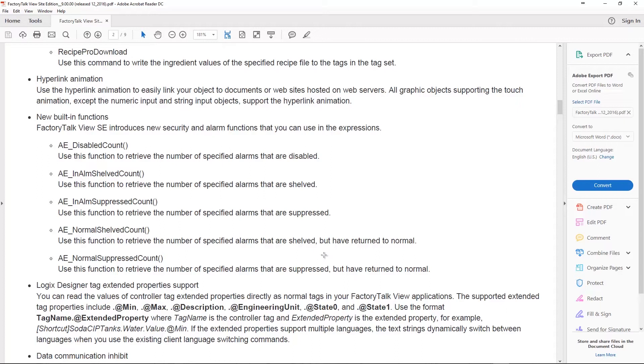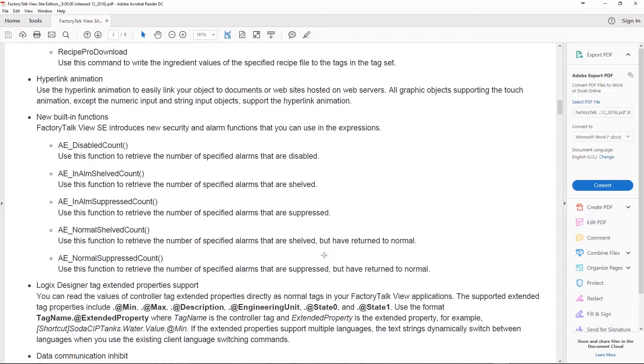But here's probably the biggest feature here of the version 9.0 is the Logix Designer tag extended property support. So you know for a while now in Studio 5000 we've been able to add an @Min and @Max and @Description and @Engineering Unit and @State to our tags. This is all kinds of stuff we used to do with HMI tags but once we get direct referencing with Logix, why would we want to create a tag database anymore? But on the flip side the downside was we still by doing direct referencing we had no way to do a min, a max, a description and whatnot like we did with HMI tags. But now with version 9 of View SE we can actually access those tags extended properties, which is very cool. Not only cool for us designers but also very cool for the people doing the PlantPAx process objects those face plates because that should really add some power to what they do as well.